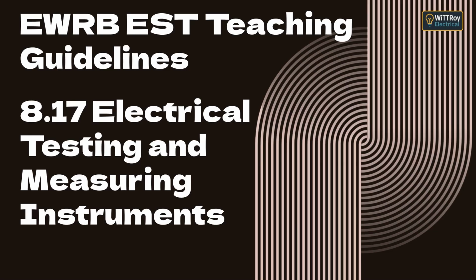Topic D. Safety categories, CAT ratings. Now let's move to Topic D. Safety categories, also known as CAT ratings. Every test instrument must meet a minimum safety category depending on where it's used. Here's how to say it clearly. CAT 2 instruments are suitable for socket outlets and appliances. CAT 3 instruments are for distribution boards and fixed wiring. CAT 4 instruments are for testing at the origin of the installation, for example, main supply and switchboards. Always choose an instrument with the correct CAT rating for the environment. Using a lower rated meter on a high-energy circuit can result in an arc flash or instrument failure. As a rule of thumb, for switchboard testing, always use CAT 3 or higher.